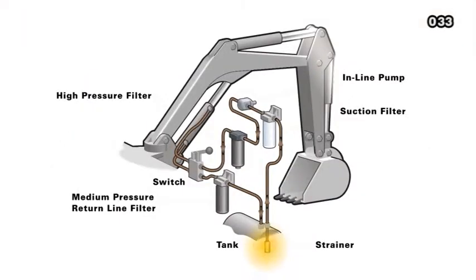Looking at this animated hydraulic circuit, note how the oil is drawn through a strainer in the tank, which removes larger debris. The oil then goes onward into the low-pressure pump-protecting suction filter.